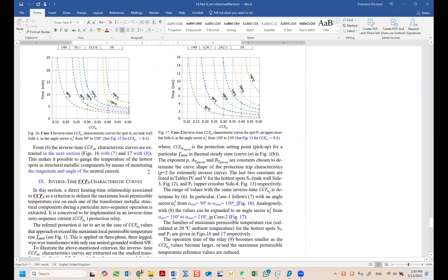Now I don't know if I'm going to find the paper. So if we have sensors placed inside and outside the transformer... Normally, manufacturers of big transformers embed a very thin fiber optic within the winding, and get the actual temperature distribution of the windings using fiber optics and a laser. That's for very expensive transformers. For a relatively cheaper transformer, you just slide the fiber optic next to the core rather than following the winding, and you only measure the top oil.